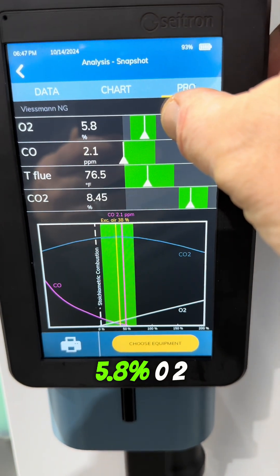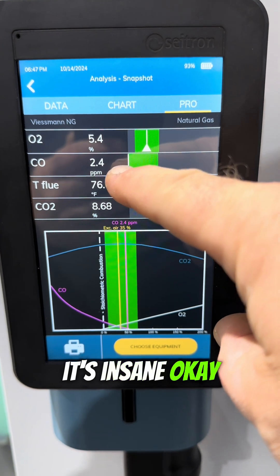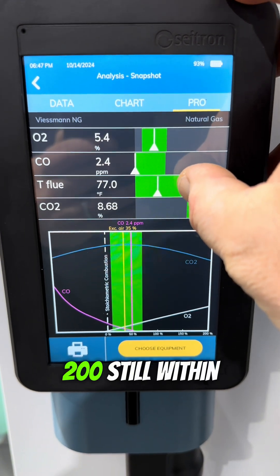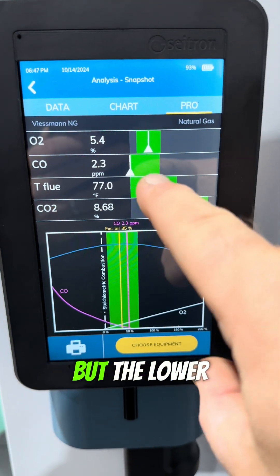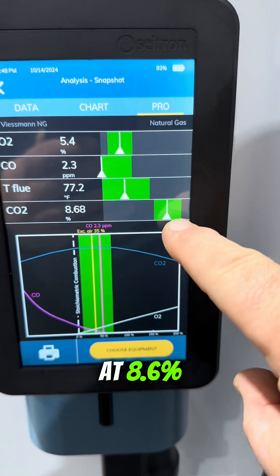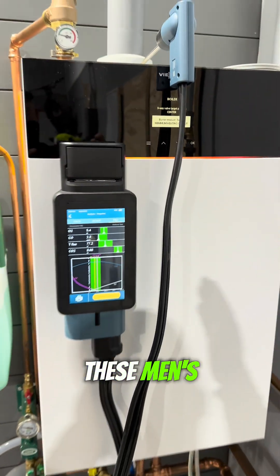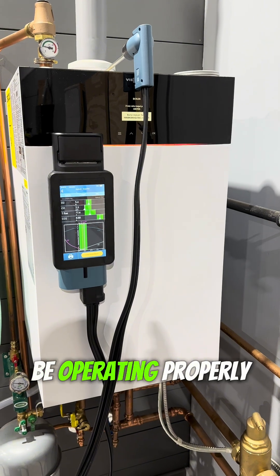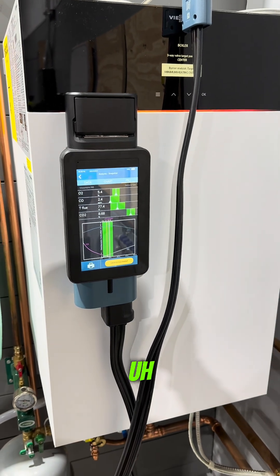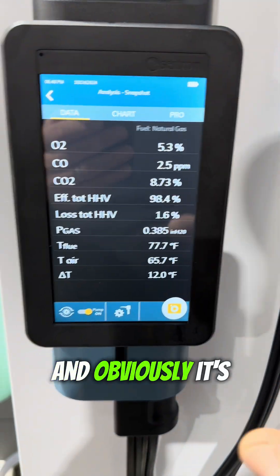As long as those indicators are showing: 6%, 5.8% O2, 2.2 parts per million CO — that's so entirely low, it's insane. That number can go up to a couple hundred without real problems — 100 easy, 200 still within reason, but the lower the better. My flue gas is measuring at 77 degrees Fahrenheit, CO2 at 8.6%. Everything is within the parameters I input based off Viessmann's numbers for it to be operating properly. If it weren't operating properly, you could adjust things like the gas input at the valve, but we don't need to make any adjustments.